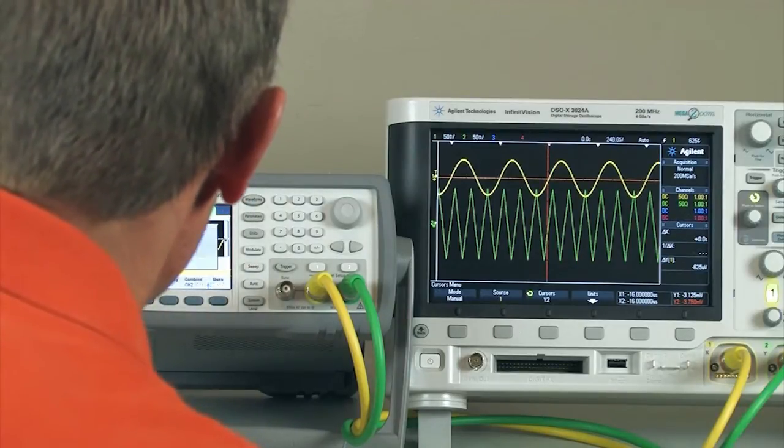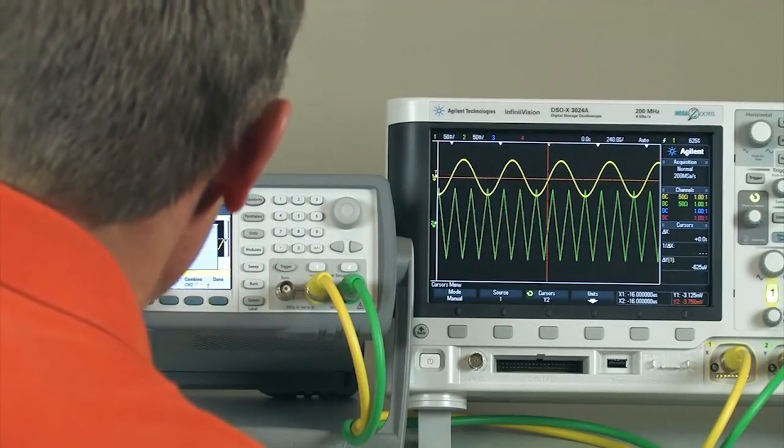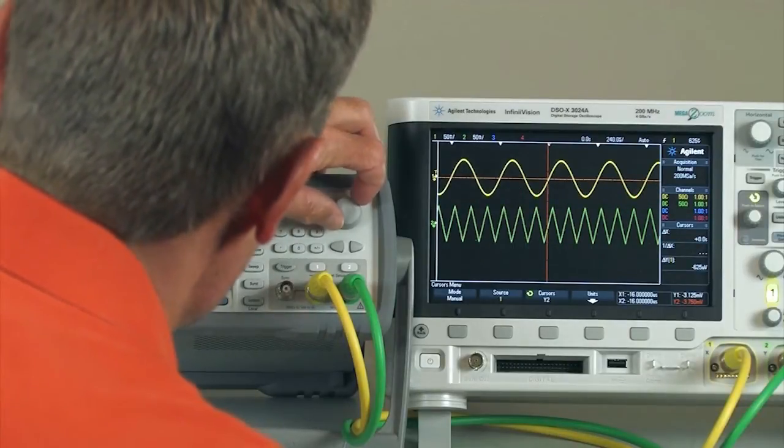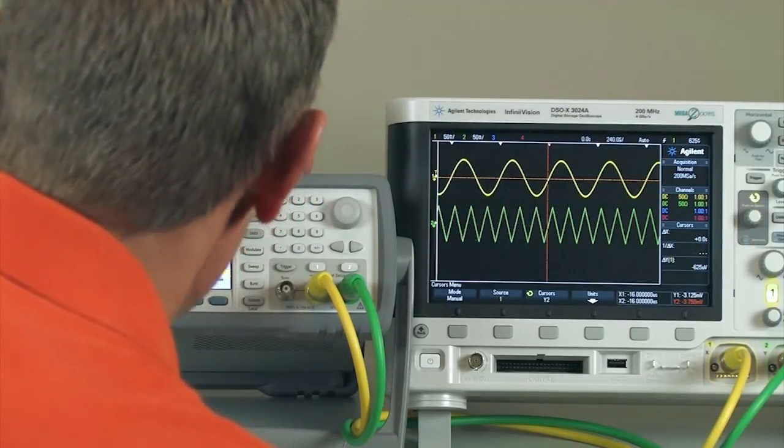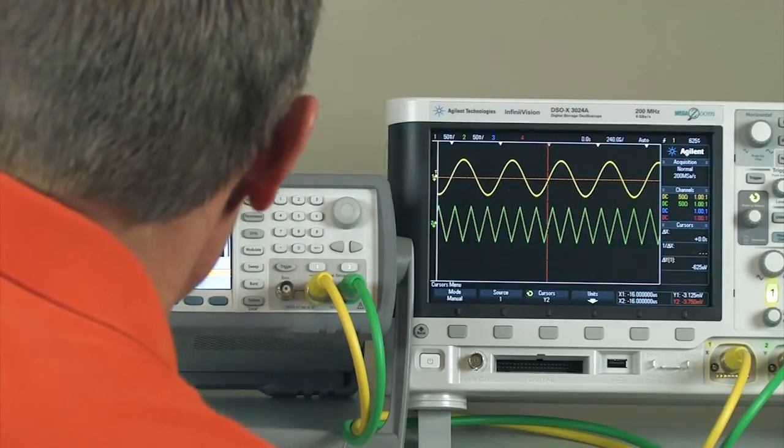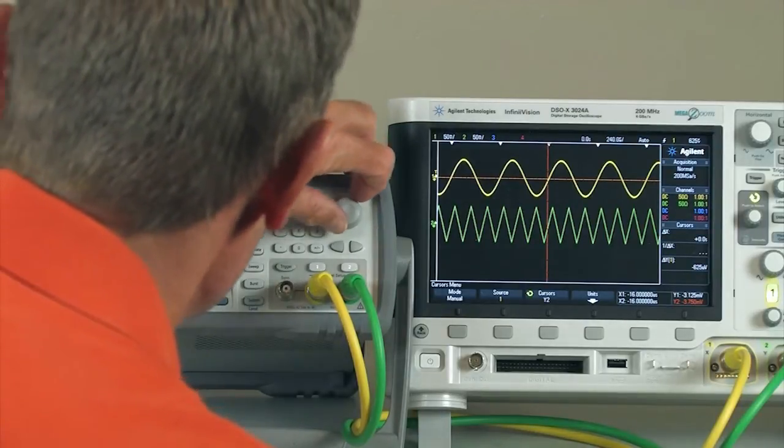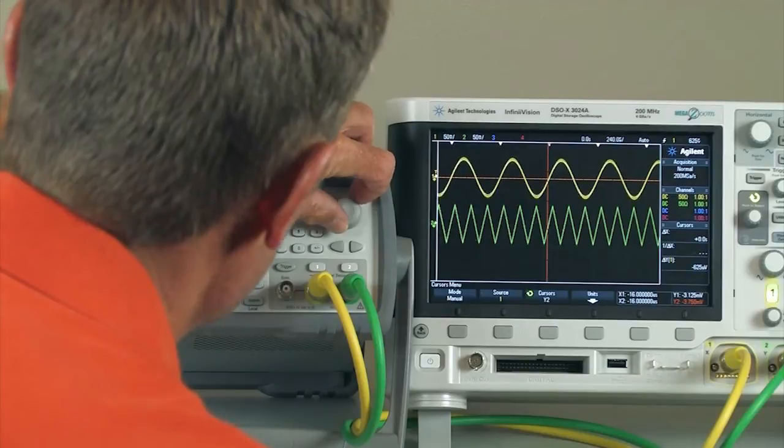So let me turn on amplitude coupling. It's an independent setting, but as you can see with the amplitude coupling on, when I change the amplitude of channel one, the amplitude of channel two changes.